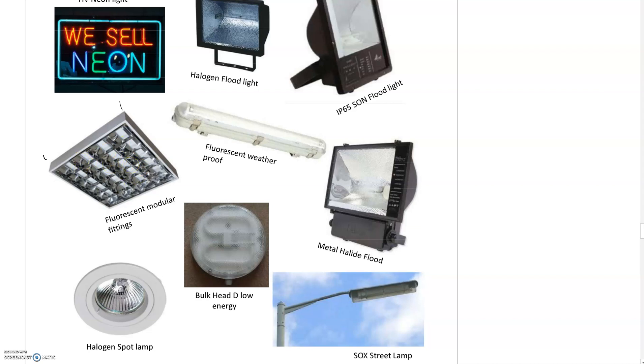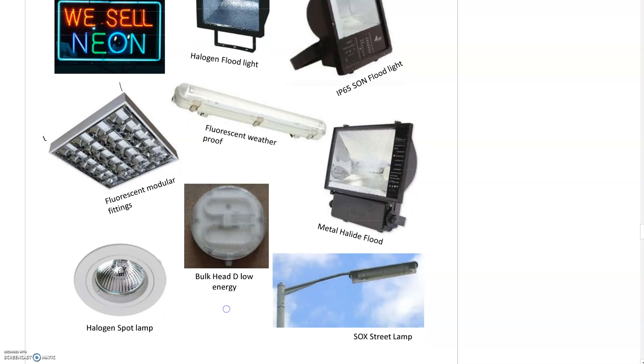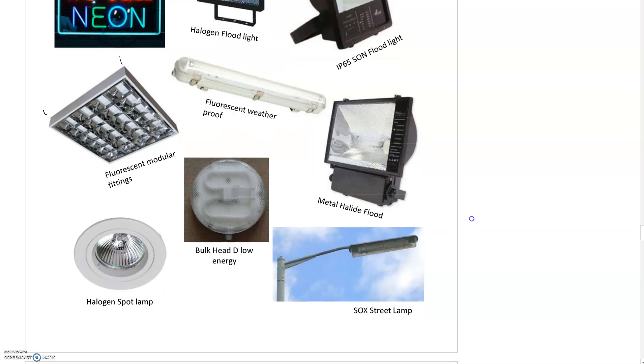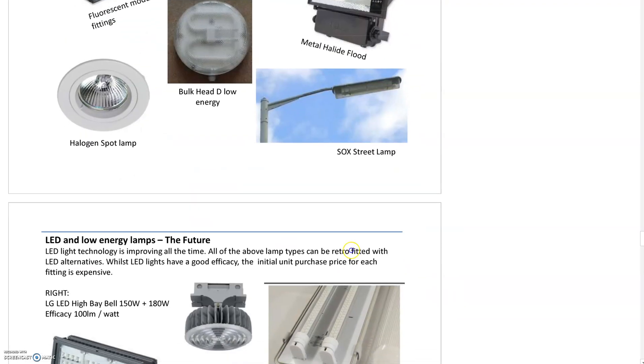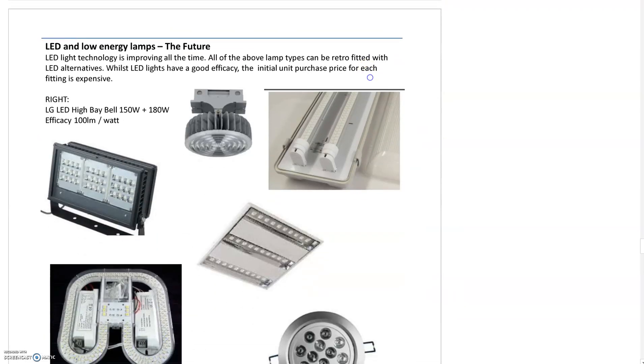These need a lot of maintenance and regular cleaning. Modular fluorescent light fittings for suspended ceilings in a 600 grid containing four T8 tubes need regular cleaning to avoid light loss. Bulkheads are used in alleyways, outdoor lighting, walkway areas, maybe public toilets. Metal halide floods give a whiter light compared to sodium's orange light.